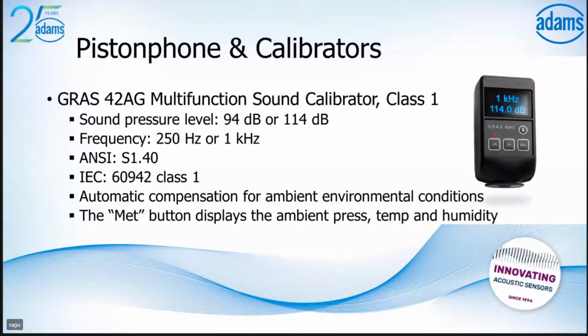So let me start with small handheld calibrators. GRAS has both piston phones and calibrators. The latest and most innovative product currently in the market for handheld sound calibrators from GRAS has a special feature: with this you can achieve 4 levels in combination. So you can do 1000 Hz 114 dB and 94 dB, and 250 Hz 114 dB and 94 dB. You can also see the temperature, ambient pressure and humidity.